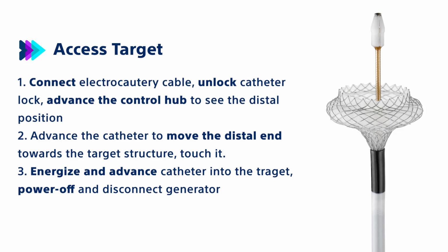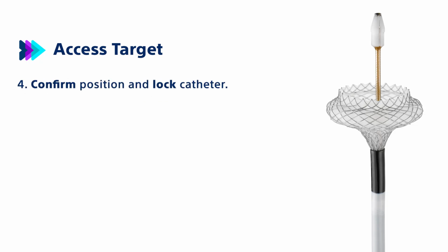visible. Continue advancing toward the target structure until it makes contact. Energize and advance the catheter into the target, then power off and disconnect the generator, and confirm the catheter tip is inside the target, at least 3 to 4 centimeters, and lock the catheter.